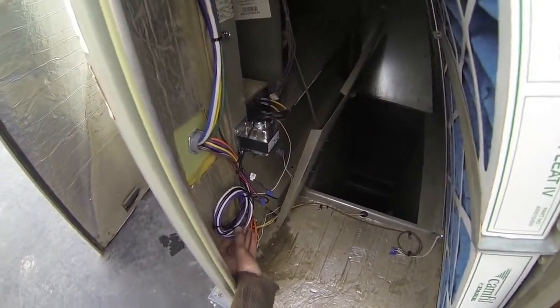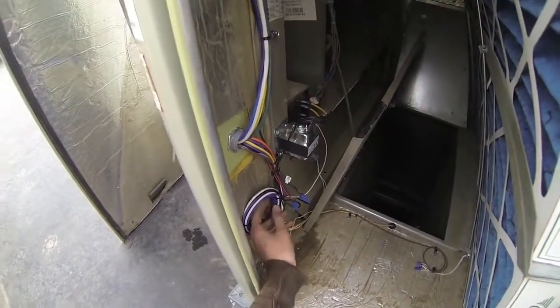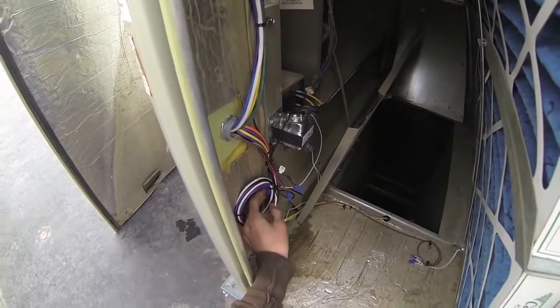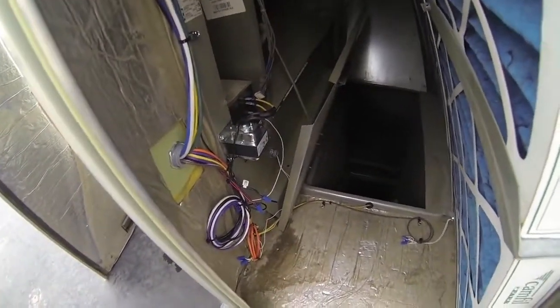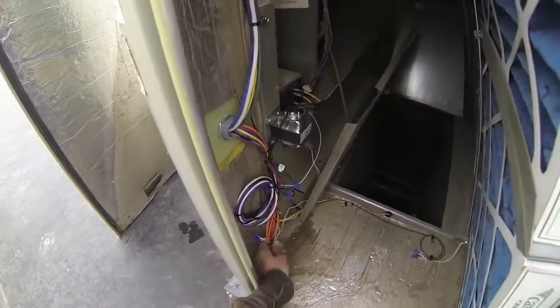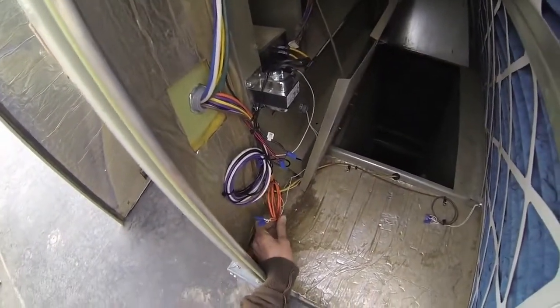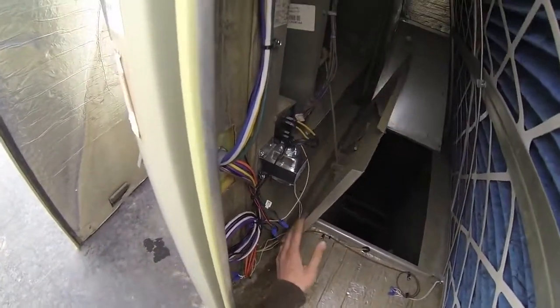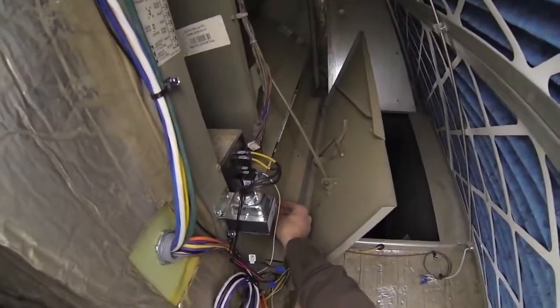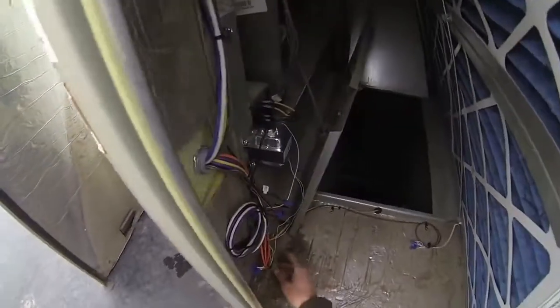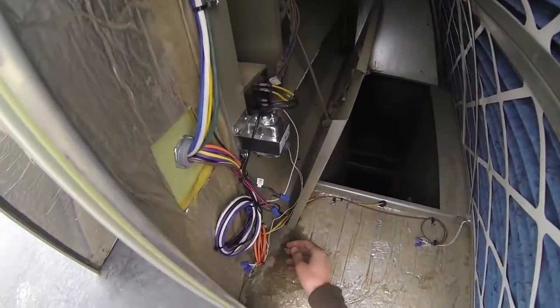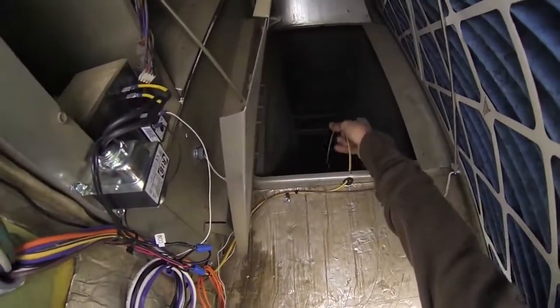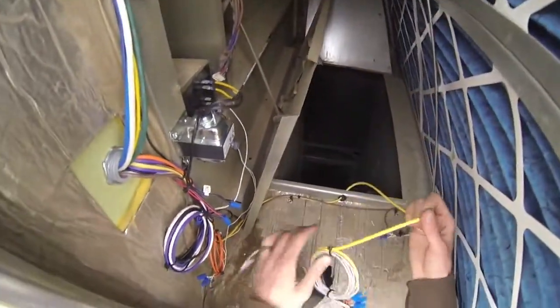We cap off the white 2 conductor and the purple 2 conductor that are not being used. White's for the power exhaust and the purple 2 is for the floating economizer actuator. Our outside air stick through and secure in the outside air hood. Wire up to our orange wire. And we have our CO2 and return wire hanging in the duct.